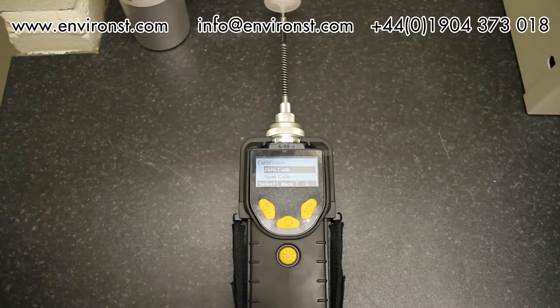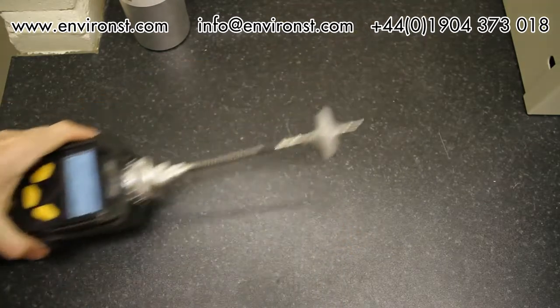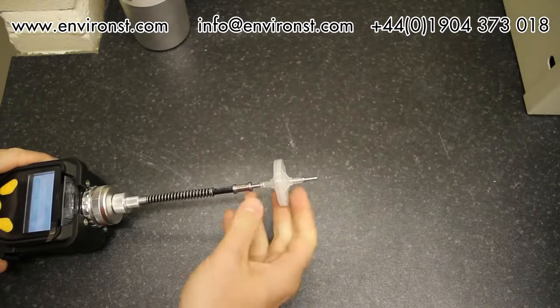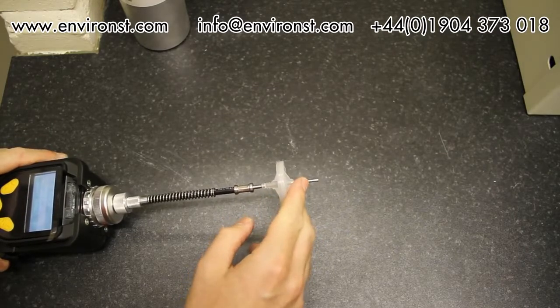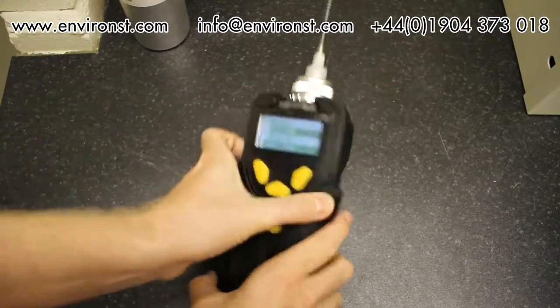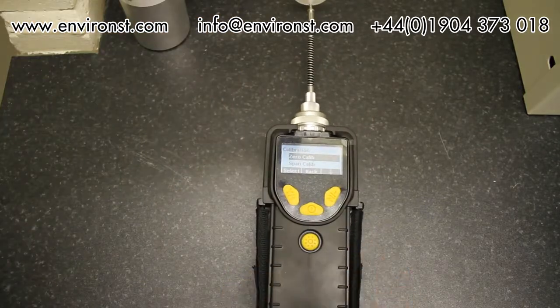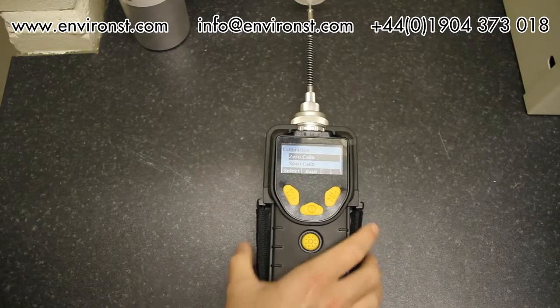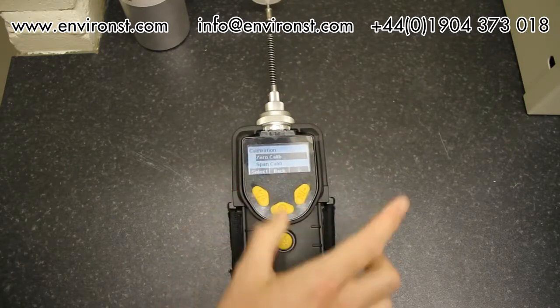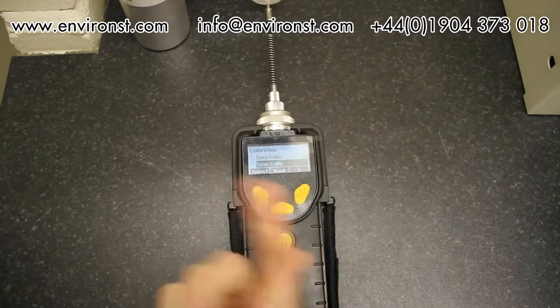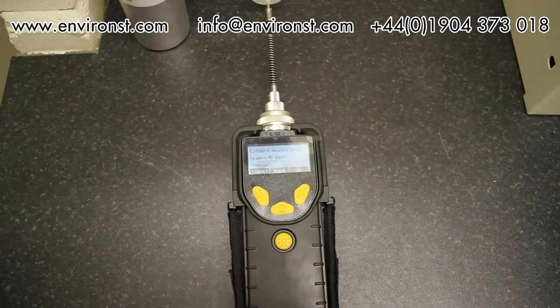Now if I want to do a 0 calibration on a ppb level instrument, I need to do things slightly differently. I need to take the instrument and apply a zeroing filter tube to the front. Otherwise, as you can see, we're in an indoor environment, we've got VOCs around. If I were to zero in that, then we would be having a falsely high 0 point, so we're not going to do that. So I'm just going to do a quick span calibration.